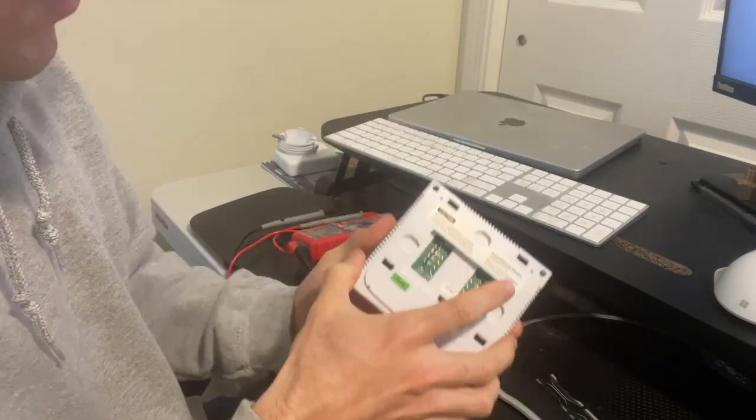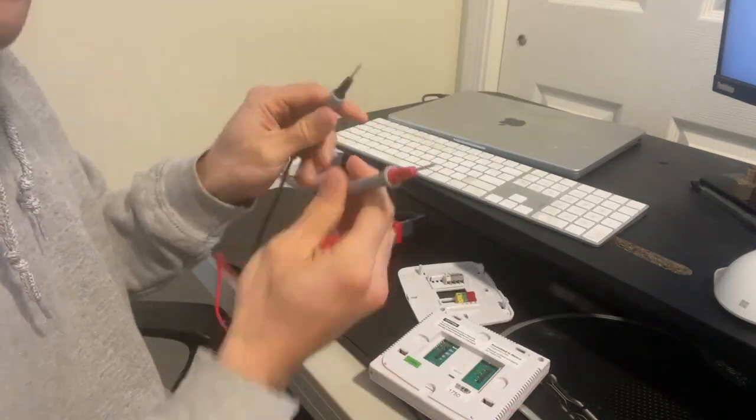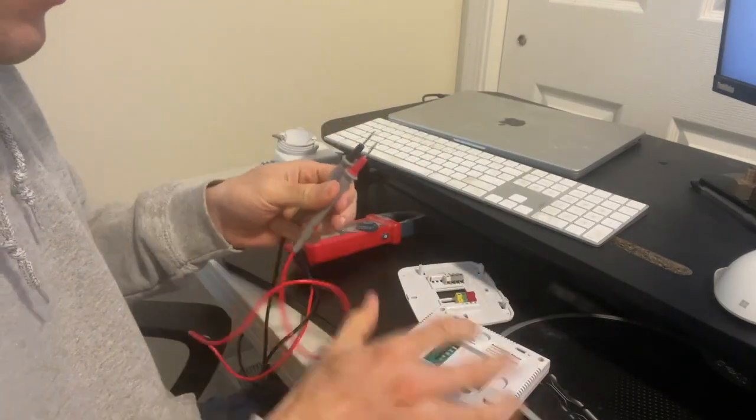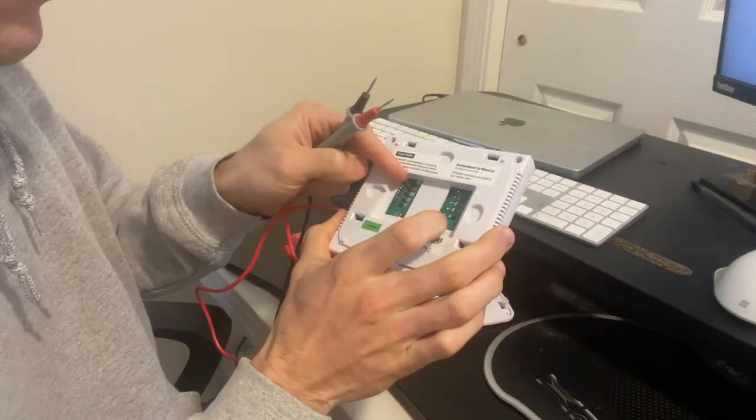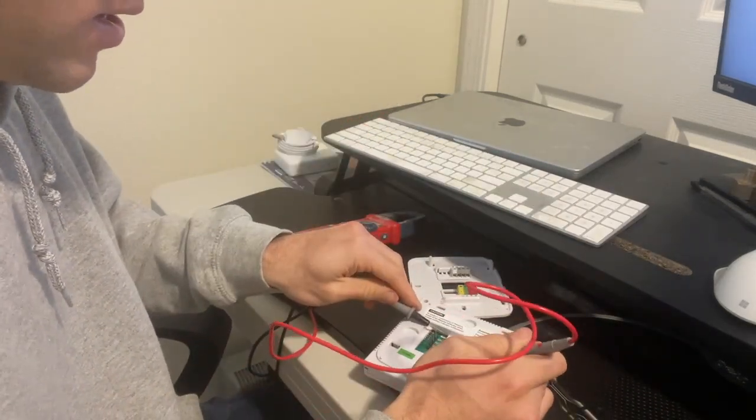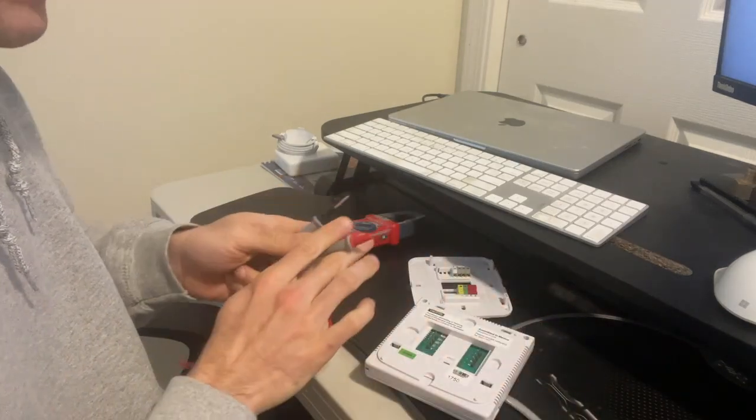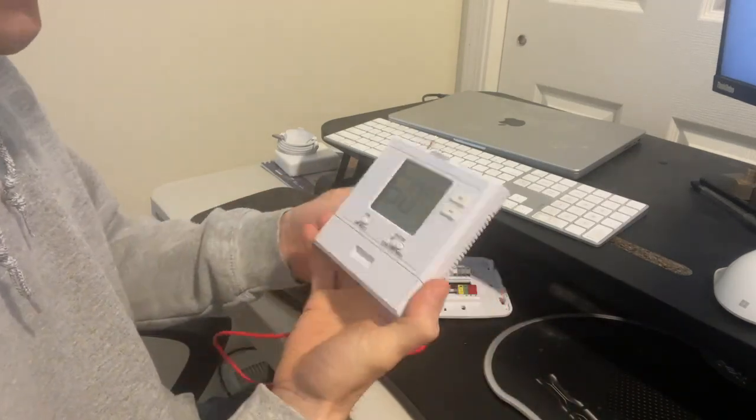So what I'm going to do is I'm going to take my probes and I'm just going to check for continuity between RH and W just like this. And so you can hear it, that we do have continuity.